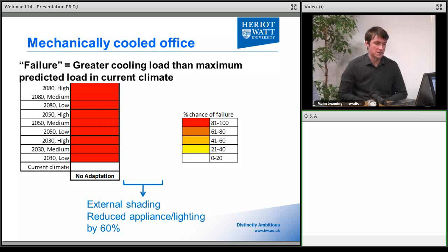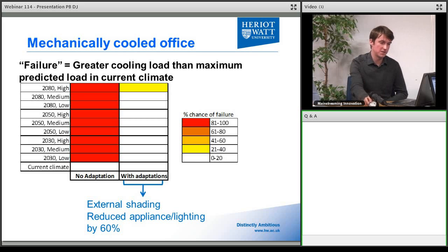Perhaps unsurprisingly, the building has a high excess cooling risk in this case. But applying similar measures, specified and designed differently - external shading and a large reduction in appliances and lighting - we make a dramatic change. The baseline building had quite high internal heat gains due to the high density of computers, and most of the improvement comes from reduced appliances and lighting.